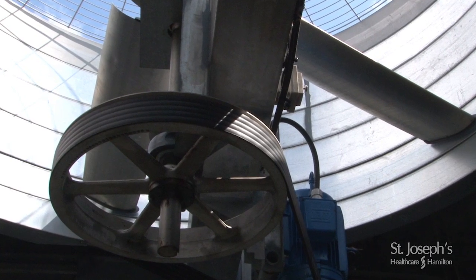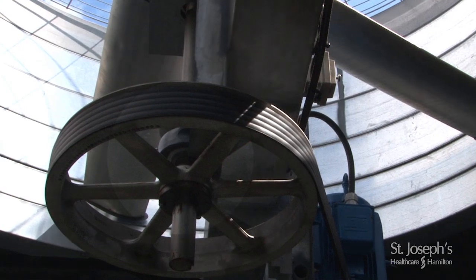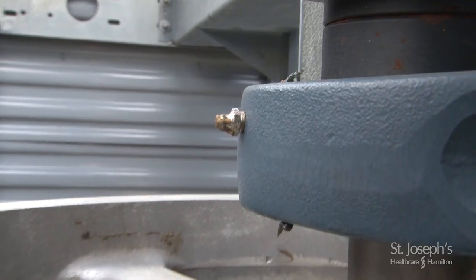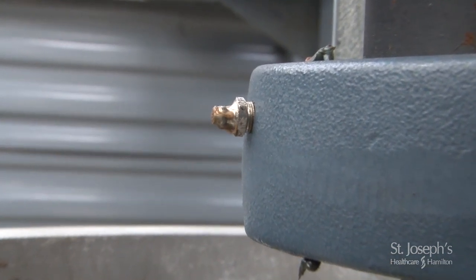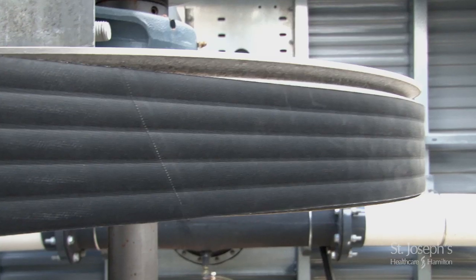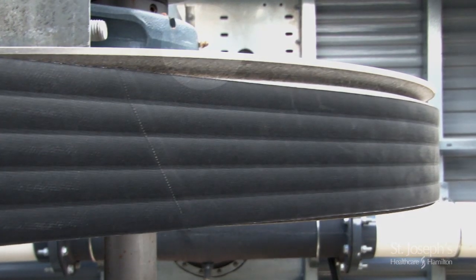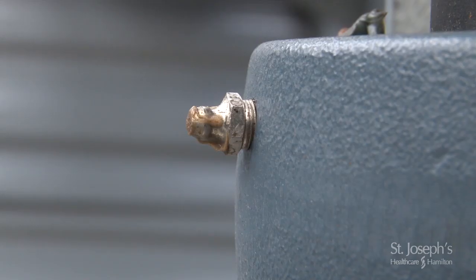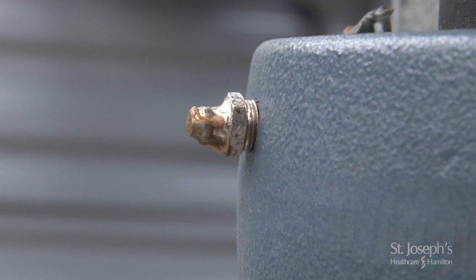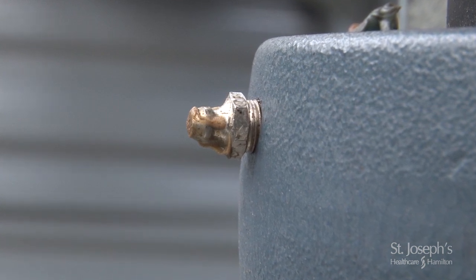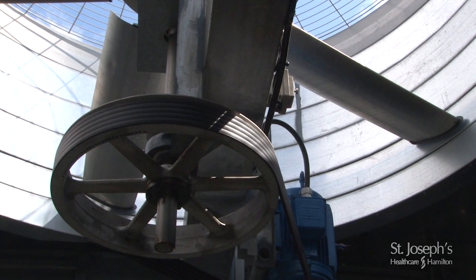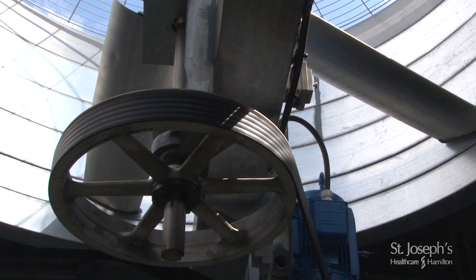What we're looking at here is the bearings on the shaft of the cooling tower. Those bearings have grease nipples on them. There's one at the bottom right here by the pulley, and then the other one's up closer to the fan assembly near the top of the shaft. Both those bearings should be greased on a twice-a-year basis. A couple of pumps from a grease gun is all that is required to keep the bearings properly greased and extend the life of those bearings.